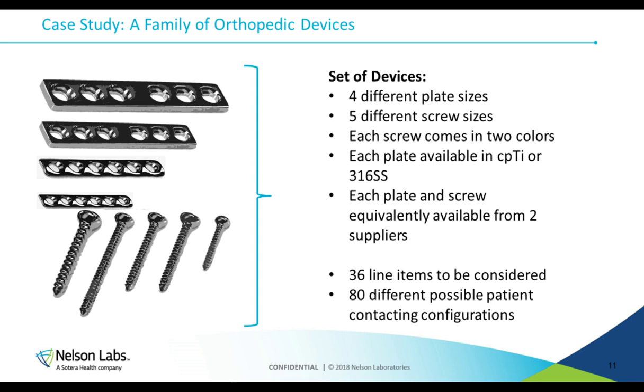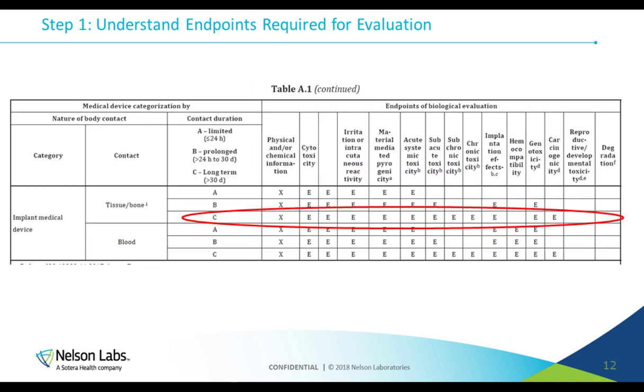But first, what we would do is say, okay, here's the set of devices. We understand how it's used. This is an orthopedic implant. It has permanent contact with tissue and bone. We'd go to table A1 of the new ISO 10993-1, which you can see there, and we would categorize it, and based off of its categorization, you can see which biological endpoints require evaluation. They're circled in red. And I just want to re-emphasize this one more time: because there's an E inside that table, it doesn't mean that you have to do all of those tests.